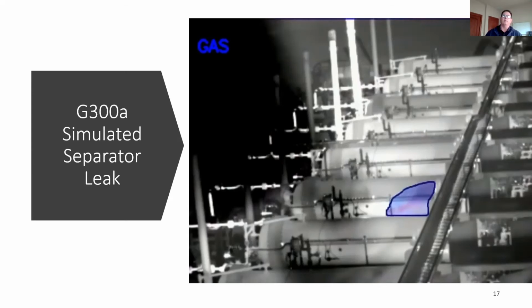So whether you believe divinely or coincidentally, about 400 of the alkanes and the alkenes, the carbon chain, the methanes, all fall at about 3.3 micron. And that's exactly what that cooler and that lens is doing: taking the mid-wave and filtering it again at that 3.3 micron for us to be able to see gas.